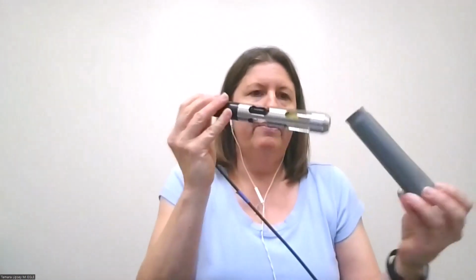This is the probe itself. As I showed you in the picture, there is a stainless steel cover that comes off if you need to get to the membrane, which most of you will never need to do, but it does come off. And then there's the cap, which has a sponge in it that will come wet. It'll just be damp. There won't be standing water in the cap, but the sponge will be wet, and that's important to protect the membrane and keep it moist.